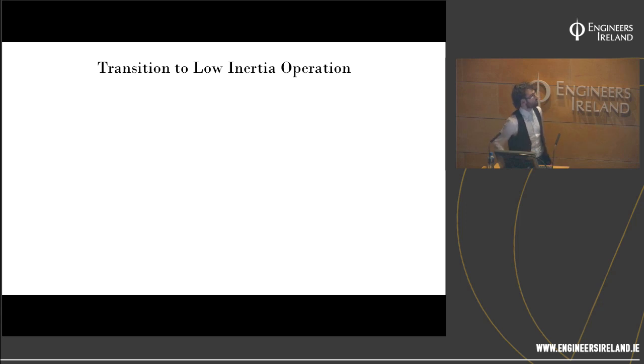Okay, so getting into our own work in UCD, I'm just going to try and characterize what happens in a low inertia power system. So if you increase the penetration of wind or PV, okay, they've two important characteristics when it comes to unit commitment and when you're scheduling the system at least cost and frequency stability. One, there's zero marginal cost. So once you give that to a cost optimization, it's going to take that free resource of energy. And two, it's non-synchronous. So they're going to displace conventional generation purely out of economics, okay?